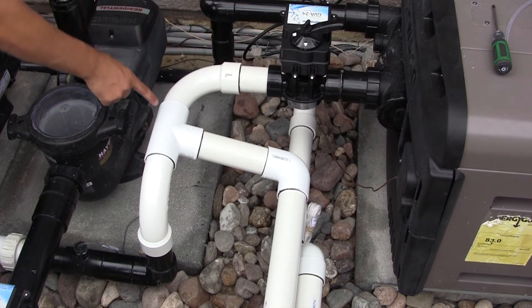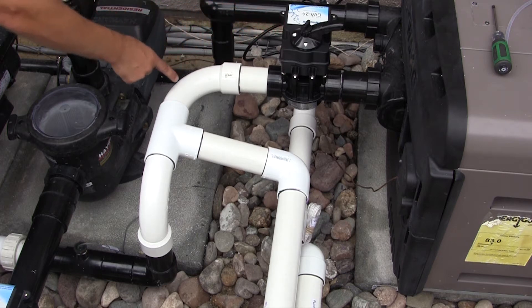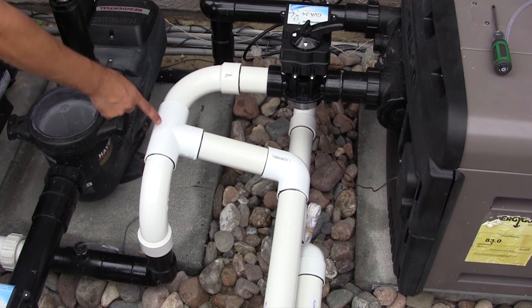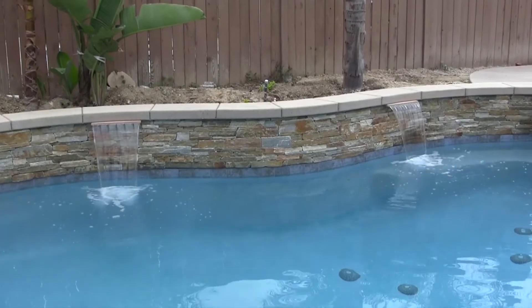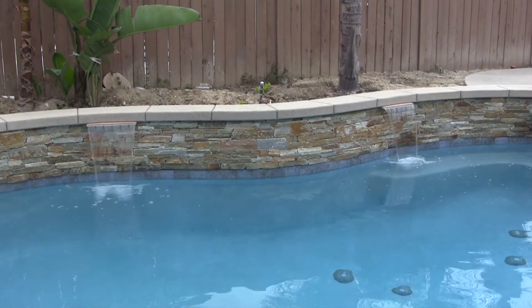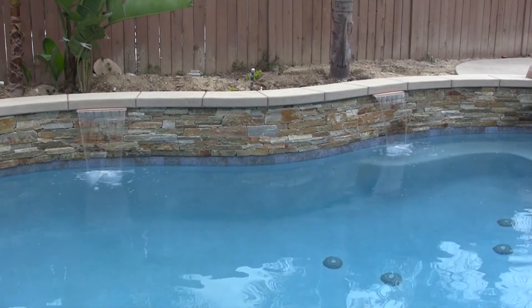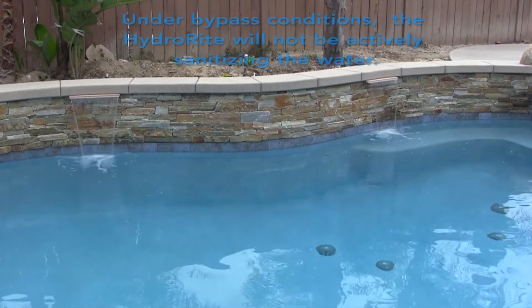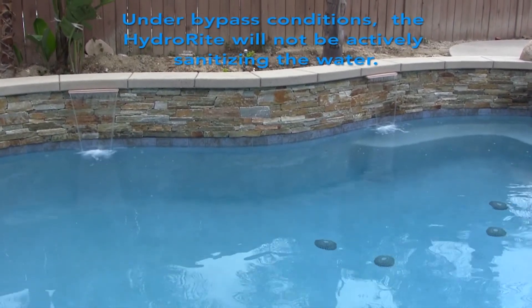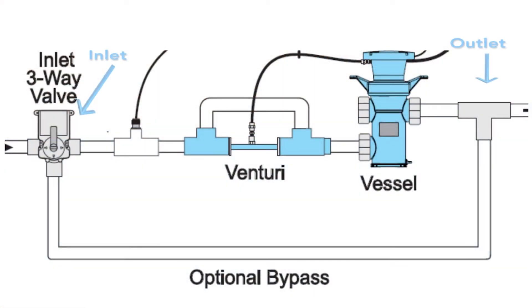Although not required, Hayward recommends that the HydroRite system be plumbed in a dedicated loop that can be bypassed, as shown on the screen. A three-way valve and actuator are supplied for this purpose. If plumbing a bypass, a T fitting will be required. A bypass will also aid in servicing and maintaining the HydroRite. Note that the increased head of the HydroRite system may affect the performance of water features installed in the pool system. A bypass will allow you to divert water directly to water features when high flow rates are required. Note that under these bypass conditions, the HydroRite will not be actively sanitizing the water.